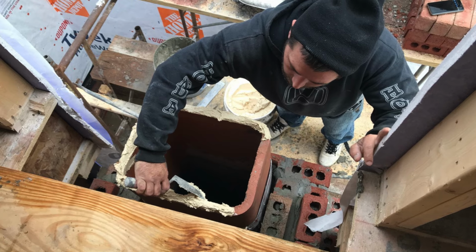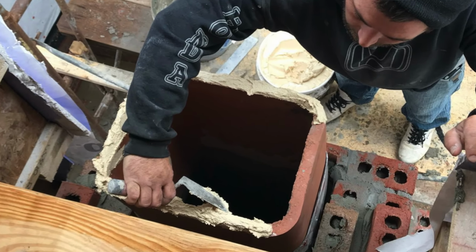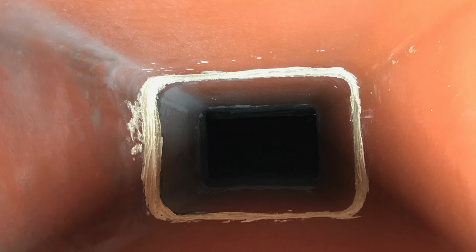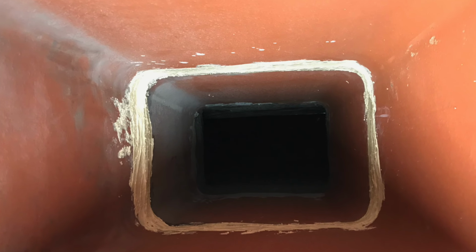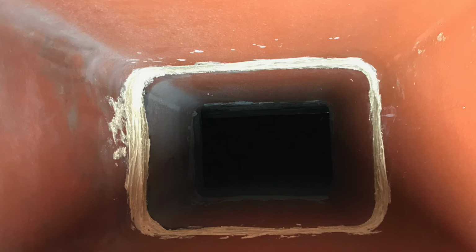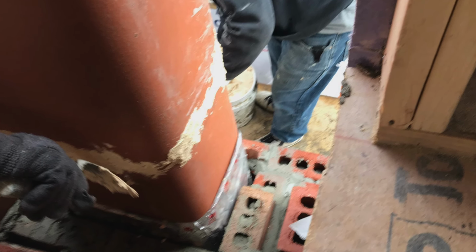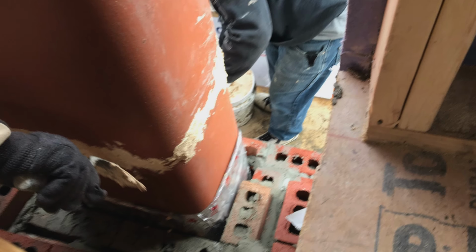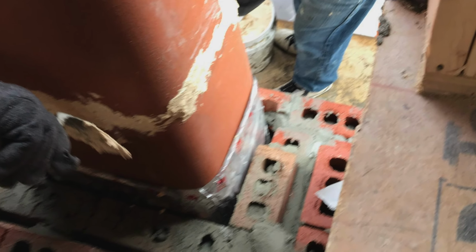The joints between clay flue tiles must be constructed with a refractory mortar specifically designed for high temperatures. These joints should measure between 1/16 inch and 1/8 inch in thickness and must be struck flush on the inside of the flue. Flush internal joints prevent soot and creosote from accumulating in mortar ledges and reduce the risk of chimney fires. The chimney walls that surround the liner must be made of at least 4 inches of nominal masonry on all sides to maintain structural integrity and provide proper heat dissipation.